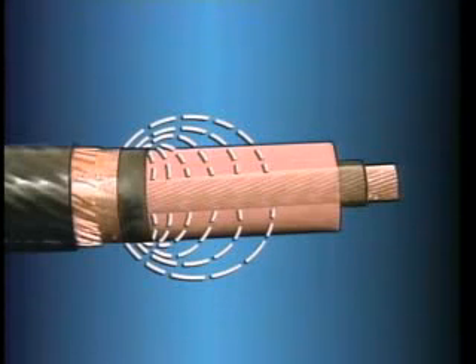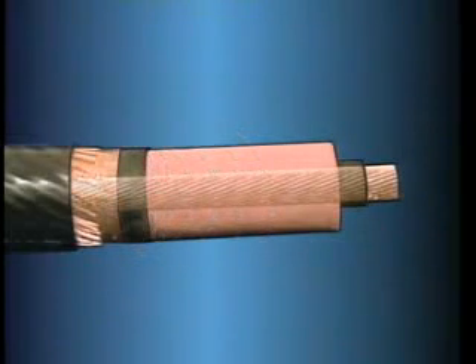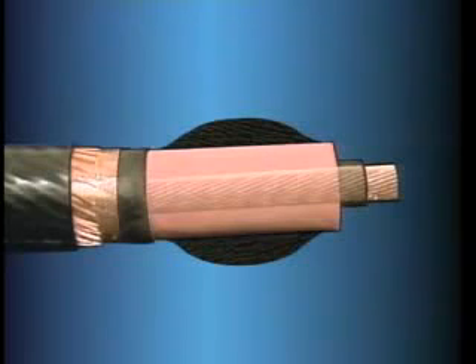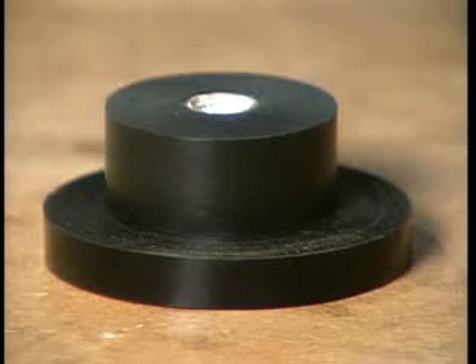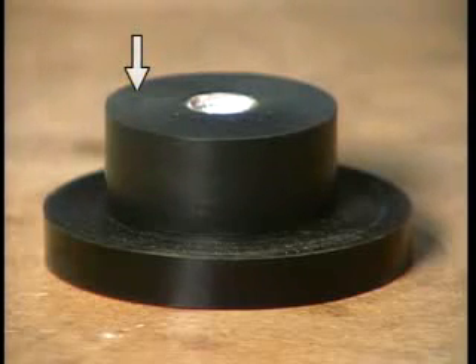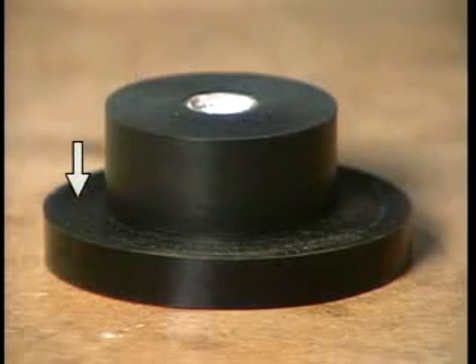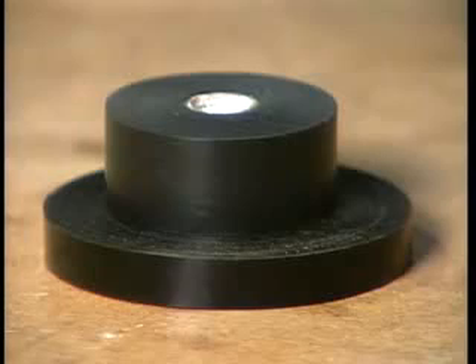There are two basic ways to control voltage stress. One way is by increasing the thickness of the cable insulation at the point where the insulation shield terminates. Insulation is added from the end of the insulation shield to a specified distance along the exposed factory-installed insulation. Layers are added so that the insulation forms a cone with a thickness specified by the termination instructions. A variety of insulation materials can be used to build the stress cone, including non-conductive rubber tape, varnished Dacron glass cloth, or other approved insulating material.